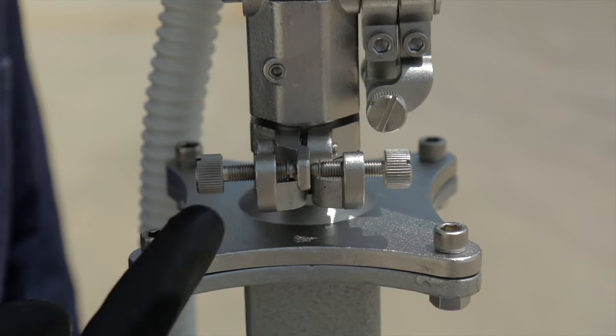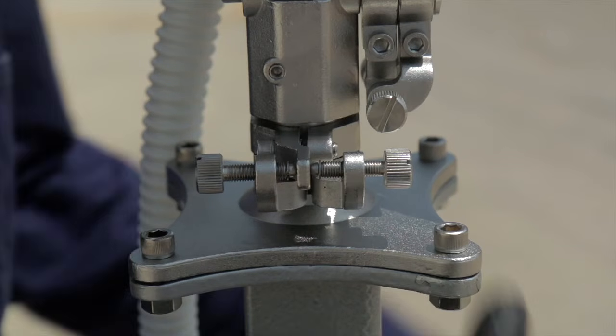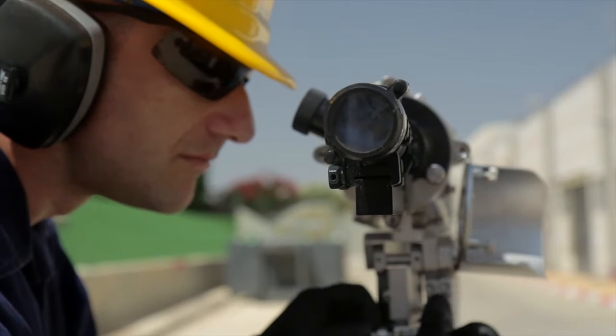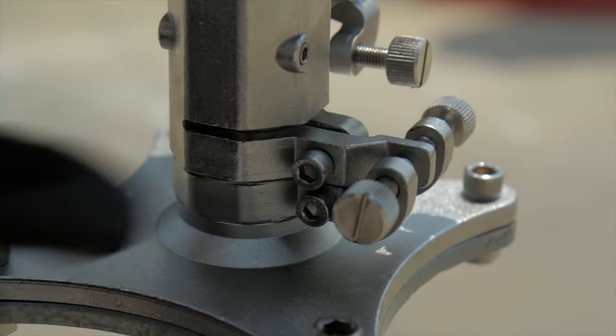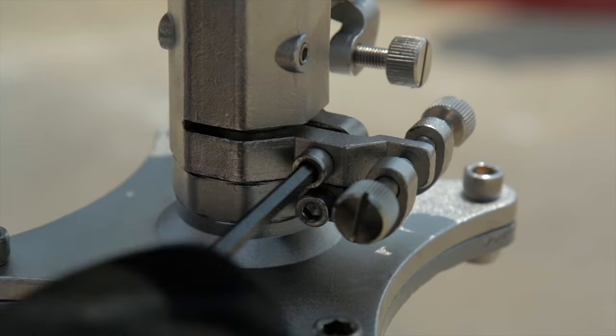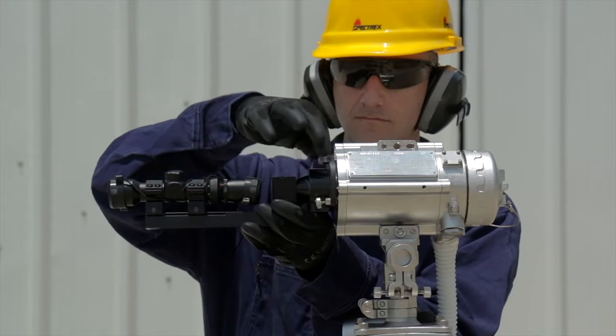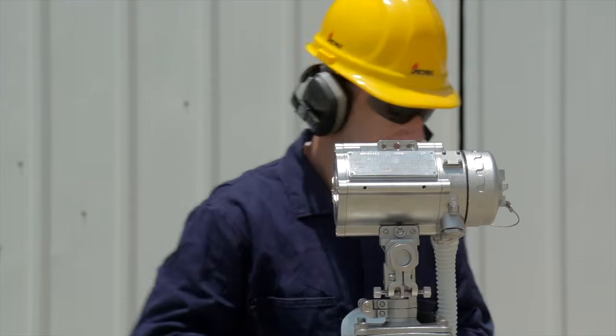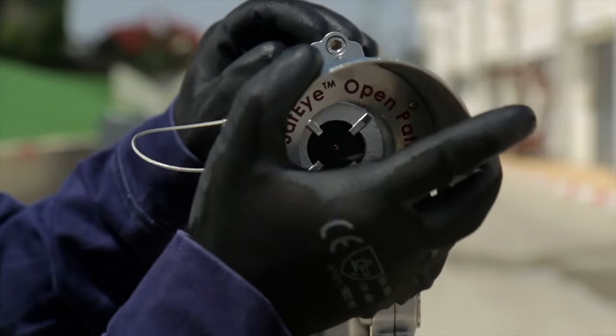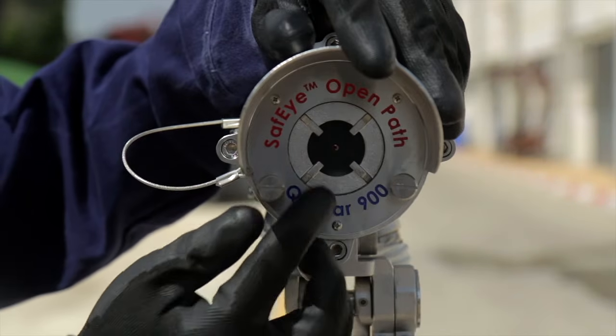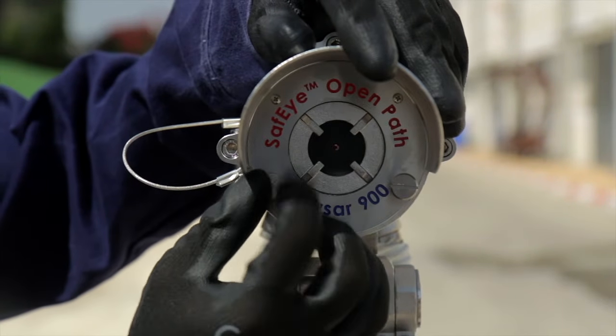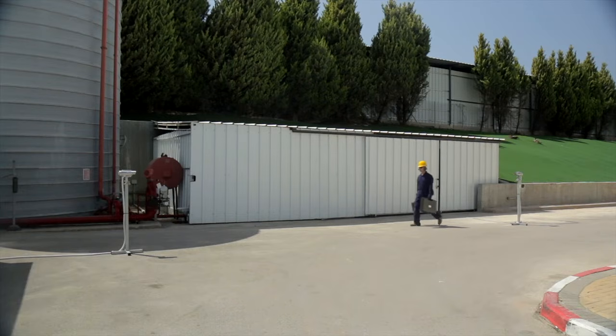Follow the same steps with the horizontal fine alignment screws. Turn the 2 fine alignment screws simultaneously in opposite directions until bringing the scope to the center of the detector. And tighten the fine alignment horizontal screw. Remove the telescope. Reinstall the front shield and tighten the 2 screws. Follow the exact same steps for the detector as well.